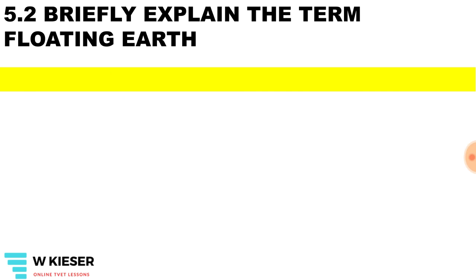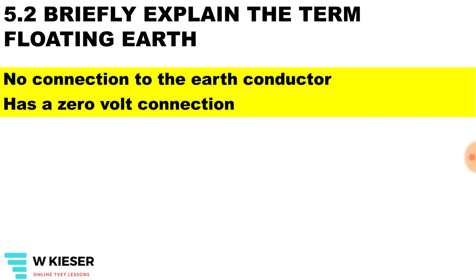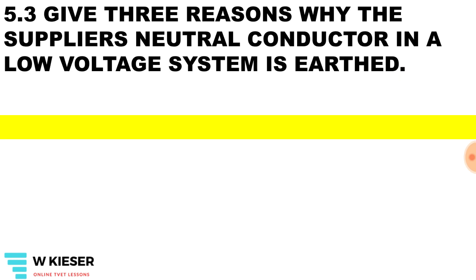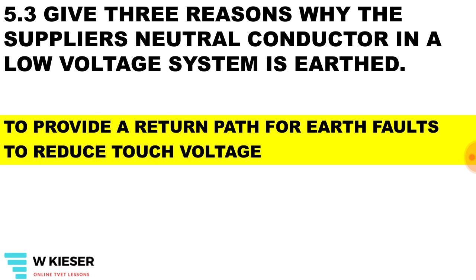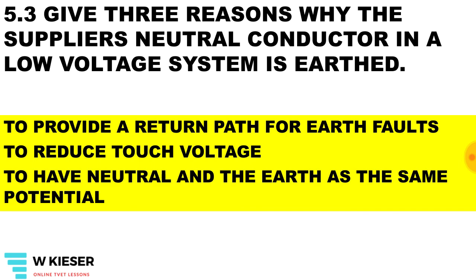What do we mean by the term floating earth? It has a zero-volt connection and there is no connection to the earth continuity conductor. Give three reasons why the supply neutral conductor in a low voltage system is earthed. It is to provide a return path for earth faults, to reduce touch voltage, and to have the neutral and the earth come to the same potential.